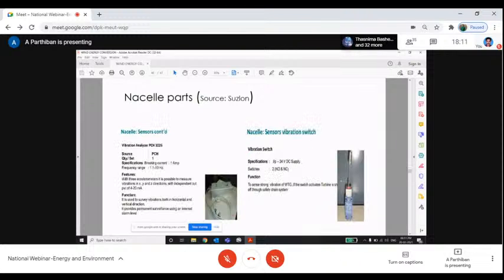These are typical vibration sensors. If there is too much vibration, this sensor will detect vibration in the X, Y, Z three directions. If it goes beyond a certain vibration, it will give a signal to the control panel to stop the turbine. If there is much turbulence in the wind, or any gust of wind, the tower will vibrate. If it goes beyond the particular vibration limit, it will give a signal to the control panel to switch off the turbine.